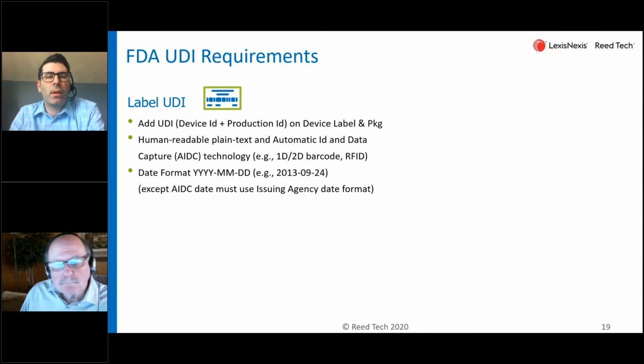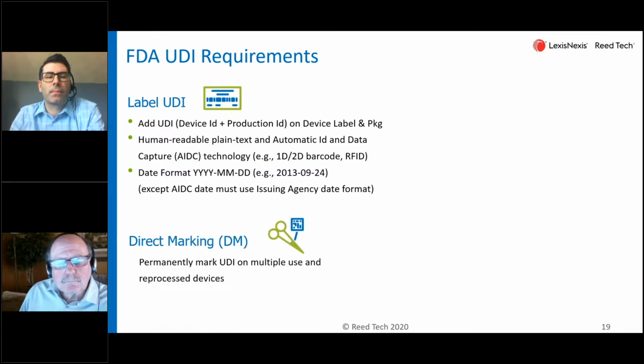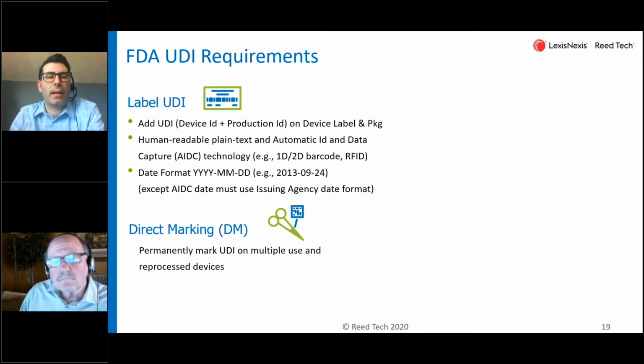So here are some of the core aspects of the FDA UDI requirements. The first one is the labeling. You would need to add both a device identifier and a production identifier on the device labeling and packaging. I do want to make a note of that: for Class 1 manufacturers, typically you don't have to include the production identifier as part of the labeling, or in the UDI really, for that matter. And as I mentioned previously, if you're currently using a UPC on your products, you can use that in lieu of UDI.